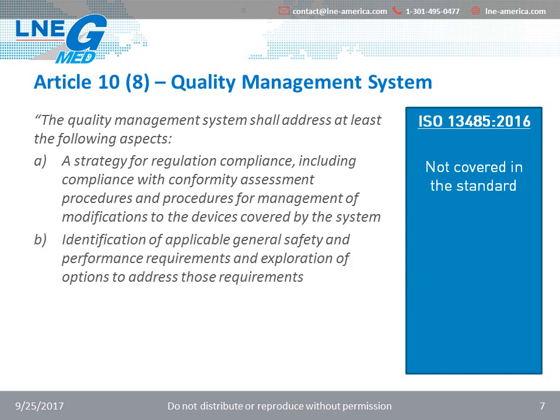The second aspect is related to identification of applicable general safety and performance requirements and the exploration of options to address those requirements. This is linked to section 7.3.3 of the ISO 13485:2016, which covers design and development inputs, and where it is clearly noted that those inputs should include functional, performance, usability, and safety requirements according to the intended use of the device. Another requirement of the QMS is to cover responsibility of the management. And this requirement is also found in Section 5 of the ISO 13485, which is entitled Management Responsibility.